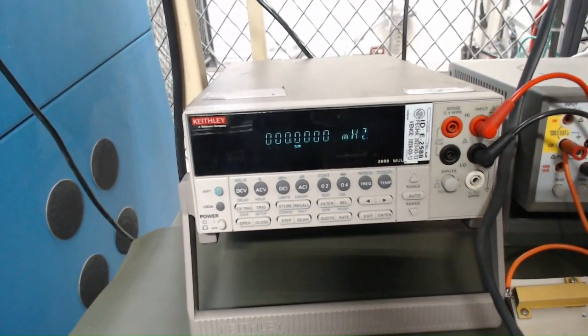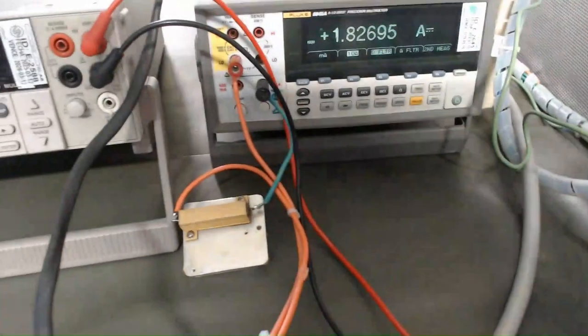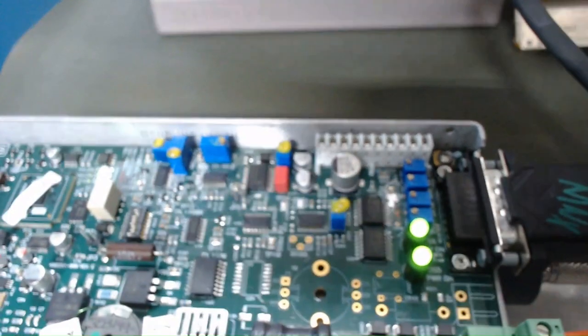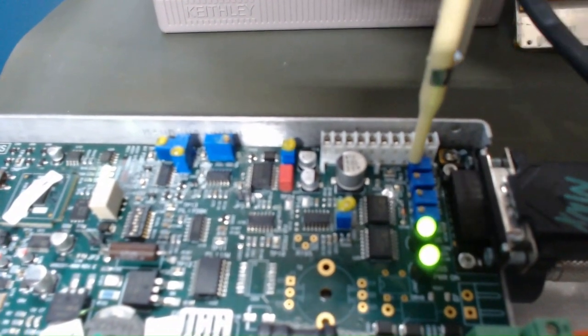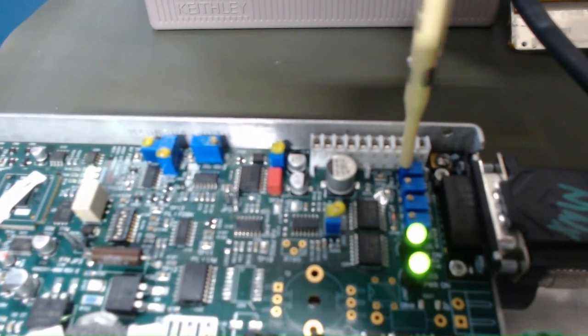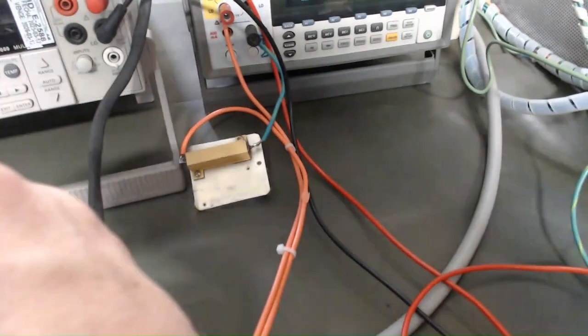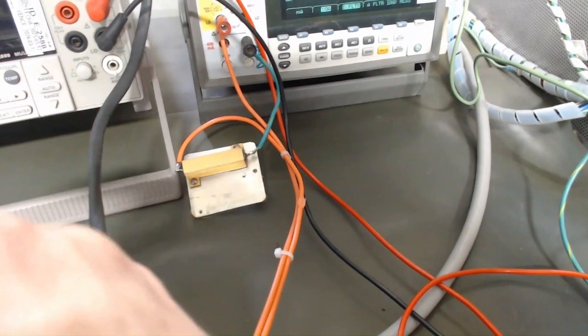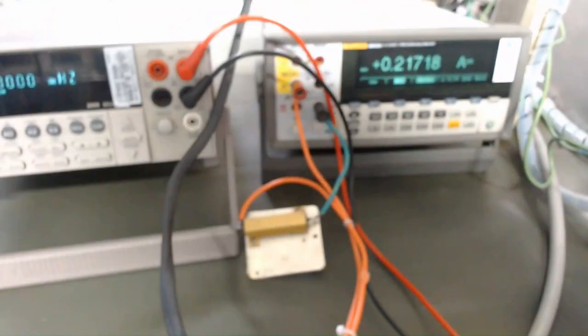As mentioned at the end of the filament test, we will exemplify how filament is preset for this model. Filament is preset to the minimum value as shown for both filament limit and filament preheat. In addition to the filament presets, output voltage and emission loop setpoint also have presets performed at the output voltage and the MA local control pots. This will be set to minimum for X6417.